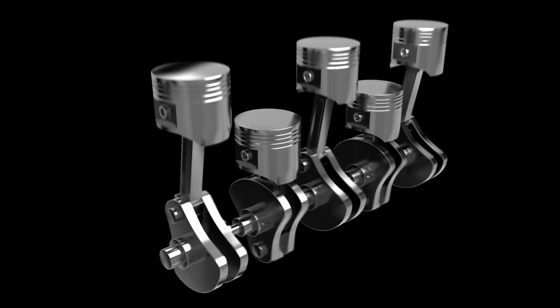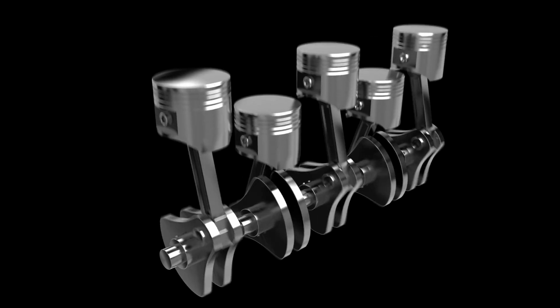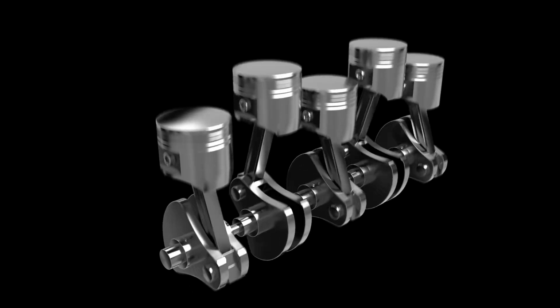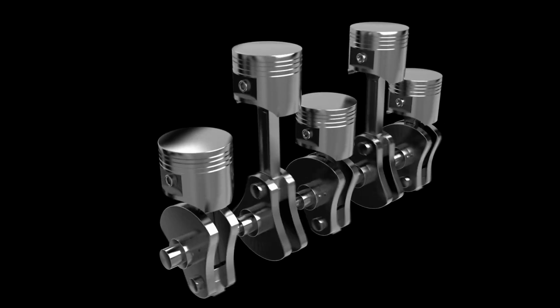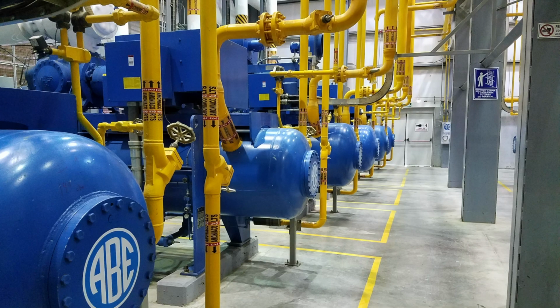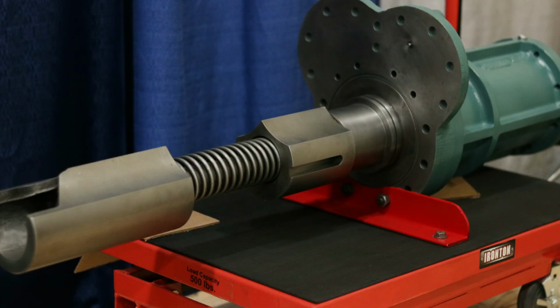Because liquid is incompressible, liquid that enters a cylinder can cause permanent damage to valves, pistons, and connecting rods. In screw compressors, liquid can damage screws and cause the rotors to separate. Liquid in rotary vane compressors may break the sliding vanes.